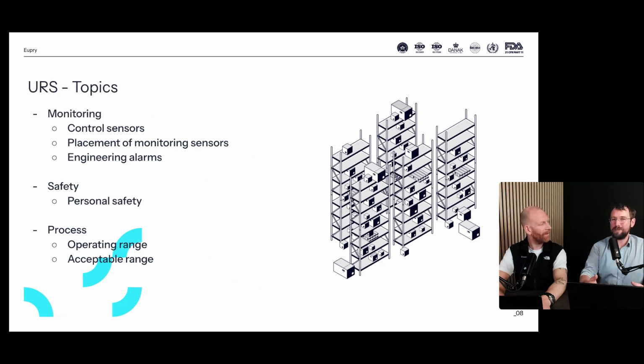I know it says so in the example in the ISPE guideline, but our basic approach is always that you do a URS in which you specify there should be monitoring in place, and the minimum number of sensors you want for your constant monitoring. Then you go all the way through the different steps we saw before, you perform a mapping, and then you decide on where the best positions for constant monitoring are.